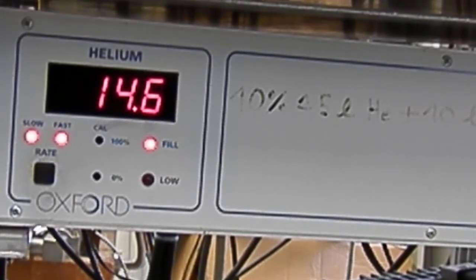What it does is measure the voltage because there is a resistor there. From there, there is a calibration, and then you can estimate how much helium you have in the magnet.